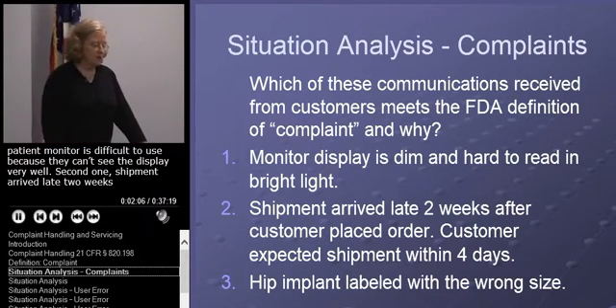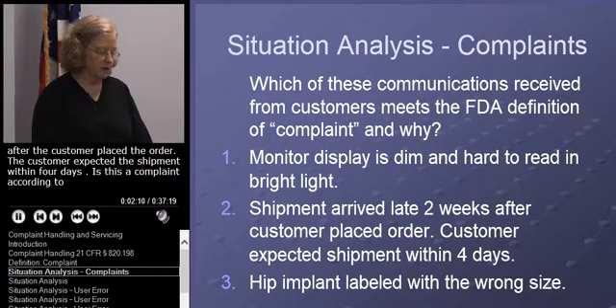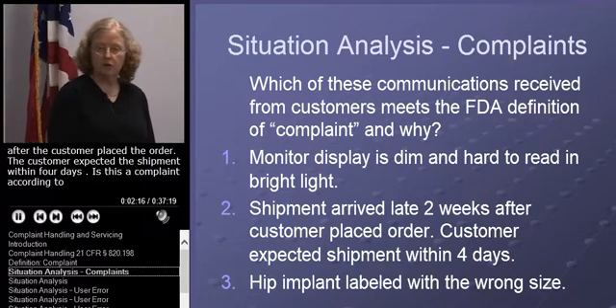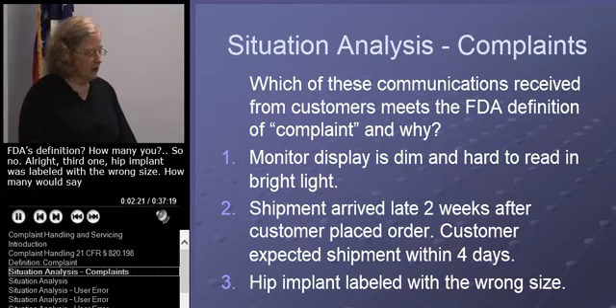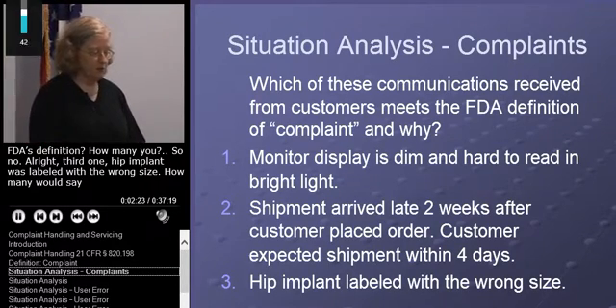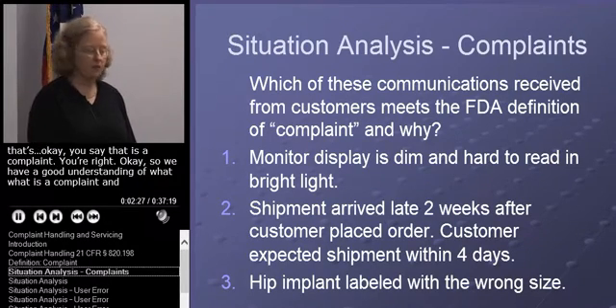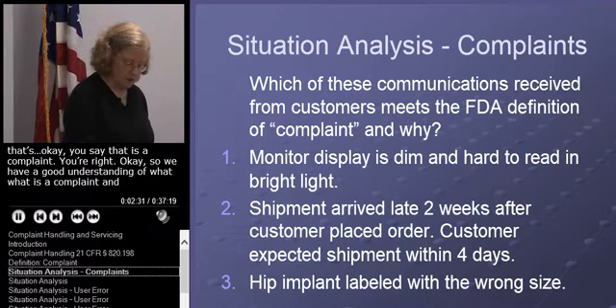The second one: shipment arrived late, two weeks after the customer placed the order — the customer expected the shipment within four days. That is not a complaint according to FDA's definition. The third one: hip implant was labeled with the wrong size. That is a complaint. So we have a good understanding of what is a complaint and what's not.